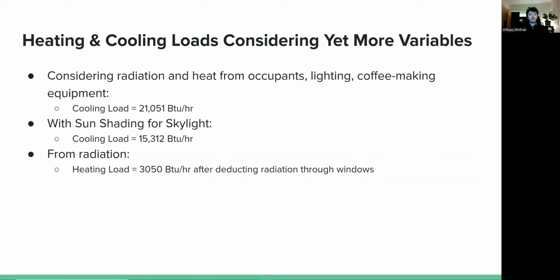Our final iteration of the heat transfer Excel design tool not only accounted for radiation in windows, but also heat given off by occupants, electrical lighting, and coffee making equipment. We found that in the summer, cooling load is 21,000 BTU per hour. In the winter, the heating load is 3,000 BTU per hour. This is due to radiation through the windows, which significantly decreases our heating load by 4,500 BTU per hour.